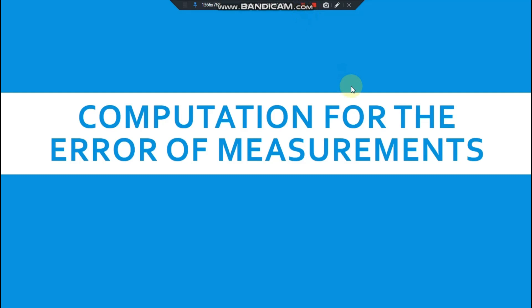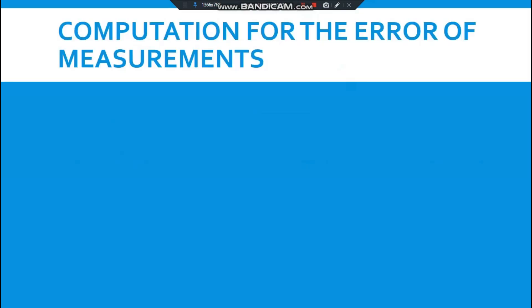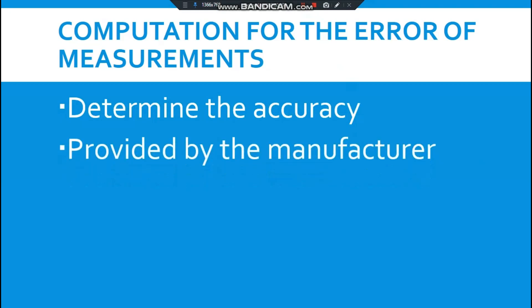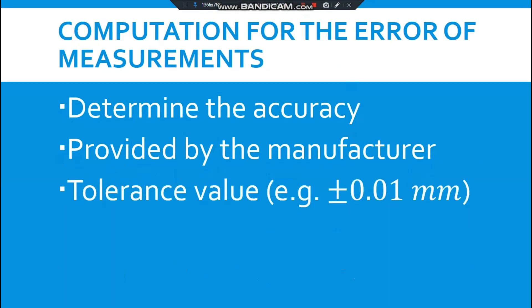Let's proceed to computation for the error of measurements. All we need to keep in mind is to first determine the accuracy of the instrument that we are going to use. One main thing to consider is the error of measurements is provided to you by the manufacturer, the instrument that you bought from. The information is typically provided in the manual. Usually it is expressed as a tolerance value, for example plus minus 0.01 millimeters.